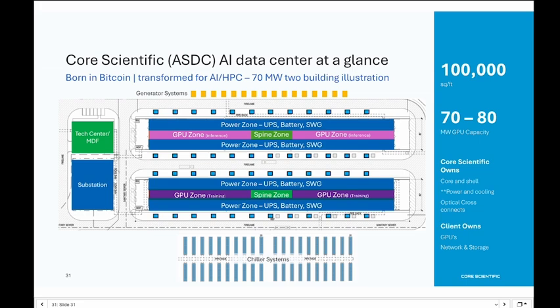So what does it look like when we transition—when we make the transformation to HPC? Well, we start landing in generators, we land in chiller systems, and we incorporate into our buildings what we refer to as power zones. These power zones are where we land the UPSs, our lithium batteries, our switchgear, etc., to power the GPUs. The mechanical plant—the chillers, generators, and battery systems—is where the incremental CapEx comes in, in order to deliver this type of infrastructure.